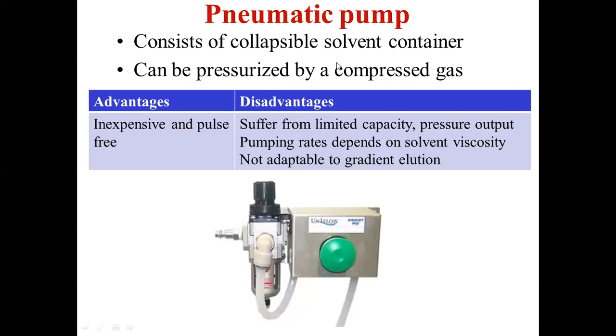And apart from that, whenever a limited flow is required, we will be using the constant pressure pump, where we cannot attain a greater flow rate. Of course, the constant pressure can be maintained throughout the separation. On the other hand, the pneumatic pump is not applicable for the gradient elution, but if we want to use the collapsible solvent container, then we can go for this pneumatic pump.